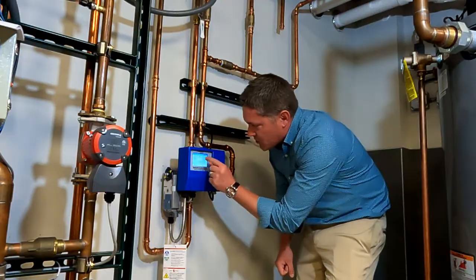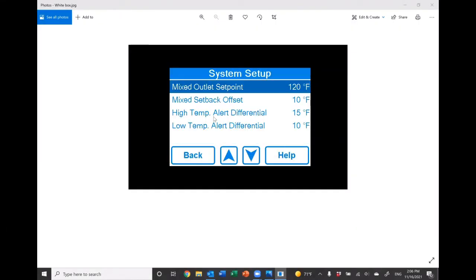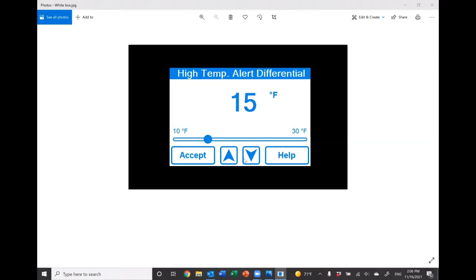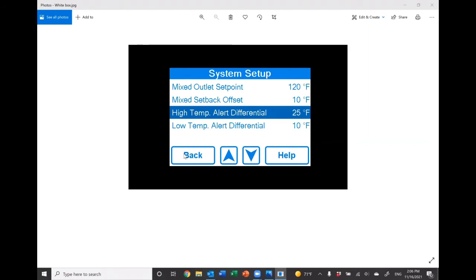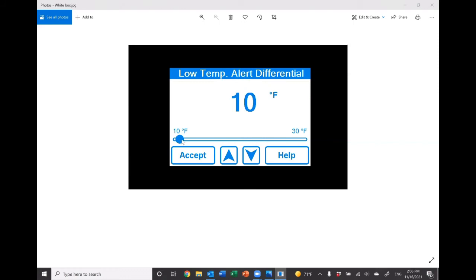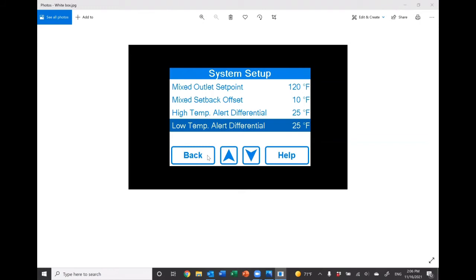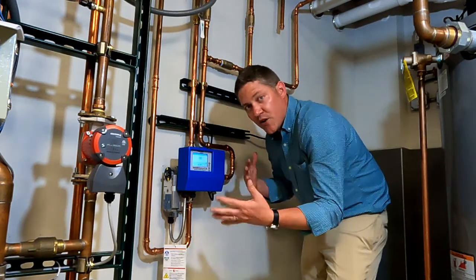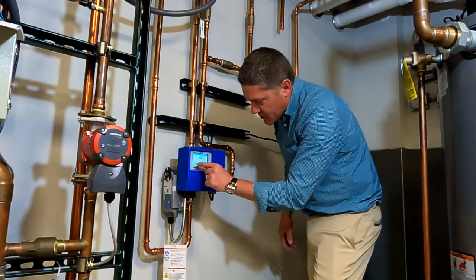degrees. Also in the programming mode, I'm in setup, in system, I have your high temp alert. If you go into high temp alert, anywhere from 10 to 30 degrees, if it spikes to whatever, say I have it set at 25, if it gets 25 degrees over the set point, this thing will shut down, recalibrate, come back on, and try to balance back in. If that happens 3 times in a row, then that's when it goes into a lockout mode. There's also a low temp alert for the same thing. If it goes too low, then it'll recalibrate 3 times and go into lockout mode, sound an alarm, and someone's got to come down and figure out what's going wrong with the valve and troubleshoot it from there.